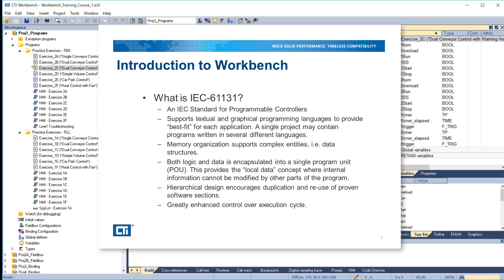What is IEC 61131? It is an IEC standard for programmable controllers. It supports textual and graphical programming languages to provide best fit for each application. A single project may contain programs written in several different languages. Memory organization supports complex entities, i.e., data structures. Both logic and data are encapsulated into a single program unit, providing a local data concept where internal information cannot be modified by other parts of the program.